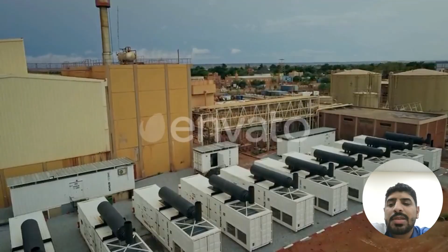To evaluate the sustainability of both systems, fuel consumption was compared under the same 1 megawatt electrical demand. Based on standard engineering assumptions, a conventional diesel generator consumes approximately 260 liters of diesel fuel every hour. This corresponds to approximately 6,240 liters every day. Over one year of continuous operation, fuel consumption exceeds 2.27 million liters.